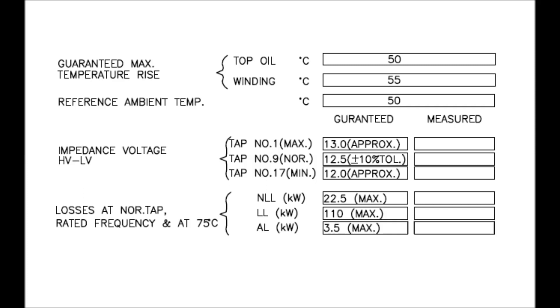Different losses are mentioned at 75°C. The maximum no-load loss is 22.5 kW — this is the calculated maximum, and the measured loss must be within this limit. The load loss, that is the copper loss, is 110 kW, which is again the maximum limit the measured loss must stay within. The auxiliary loss, including fan loss and any other losses, is 3.5 kW maximum.